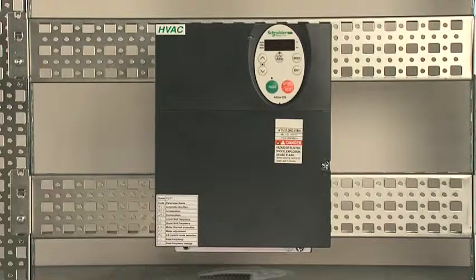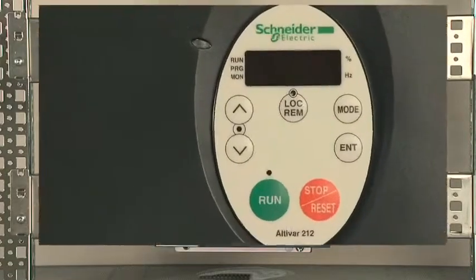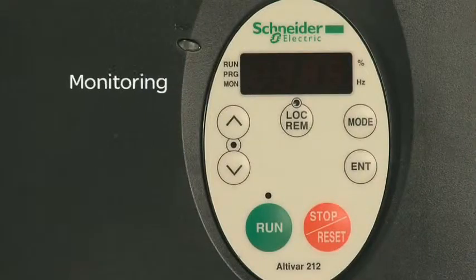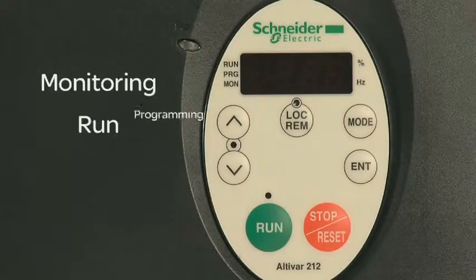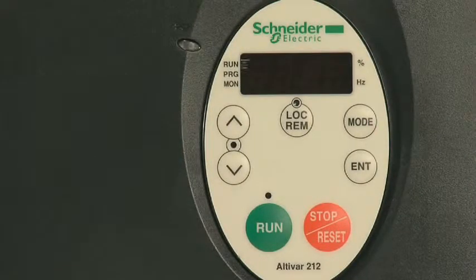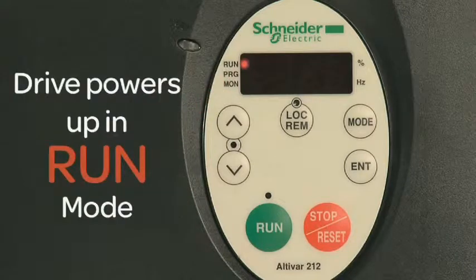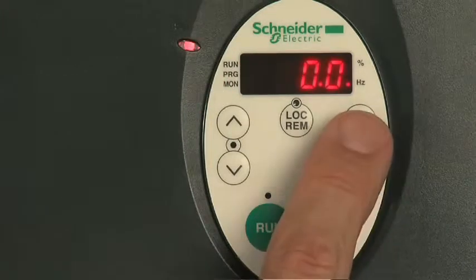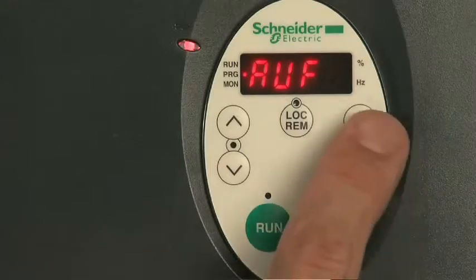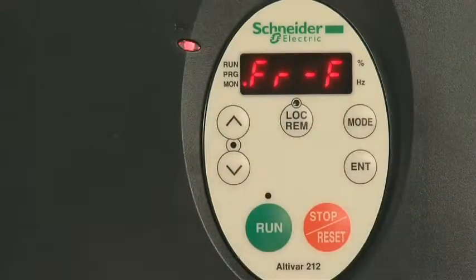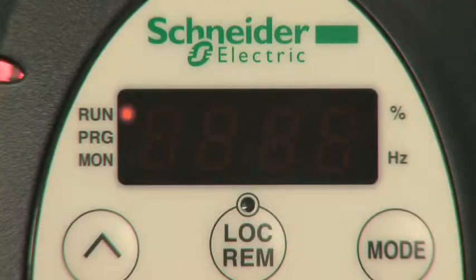The Altivar 212 embedded display terminal has 3 modes of operation: monitoring, run, and programming. The drive powers up in the run mode. To select a different mode, use the Mode key to cycle between modes. The red LED on the left side of the display indicates the current mode selected: RUN for the run mode, PRG for the programming mode, and MON for the monitoring mode.